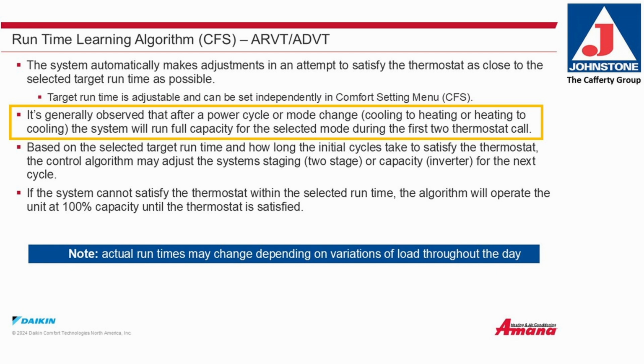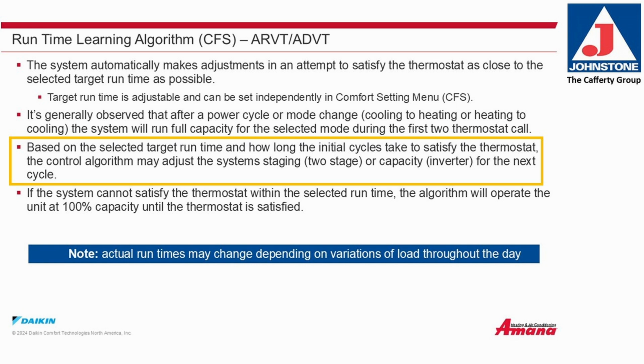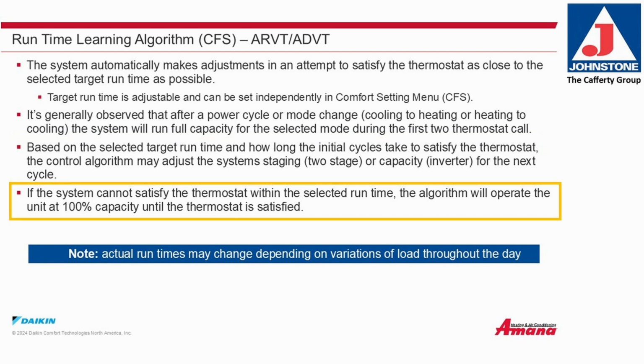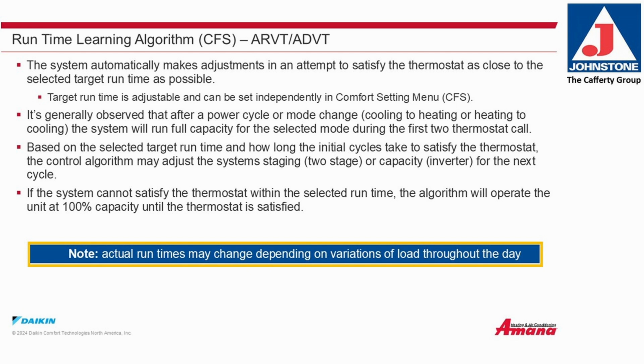Based on the selected target runtime and how long the initial cycles take to satisfy the thermostat, the control algorithm may adjust the system staging on a 2-stage or capacity on an inverter system for the next cycle. If the system cannot satisfy the thermostat within the selected runtime, the algorithm will operate the unit at 100% capacity until the thermostat is satisfied. Actual runtimes may change depending on variations of load throughout the day.